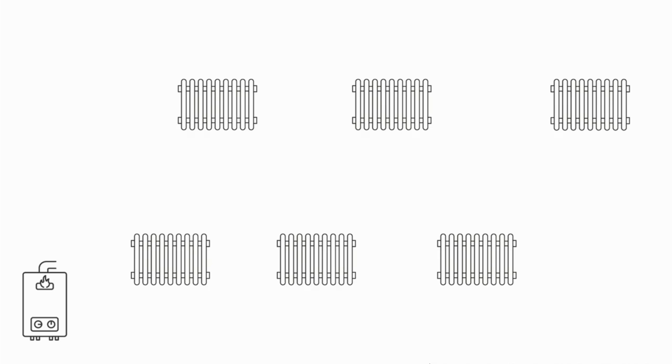What that all amounts to is that no two radiators are the same in terms of their resistance to flow. What you tend to find is that the radiators closest to the boiler tend to have less resistance to flow than ones further away, and balancing looks to even this out across the whole of the system.